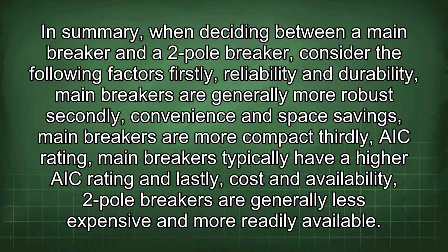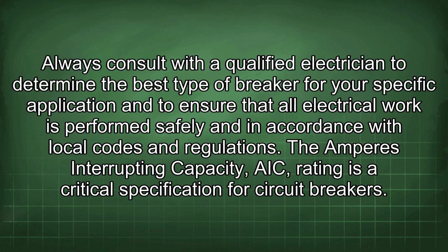In summary, when deciding between a main breaker and a two-pole breaker, consider the following factors. Firstly, reliability and durability. Main breakers are generally more robust. Secondly, convenience and space savings. Main breakers are more compact. Thirdly, AIC rating. Main breakers typically have a higher AIC rating. And lastly, cost and availability. Two-pole breakers are generally less expensive and more readily available. Always consult with a qualified electrician to determine the best type of breaker for your specific application and to ensure that all electrical work is performed safely and in accordance with local codes and regulations.